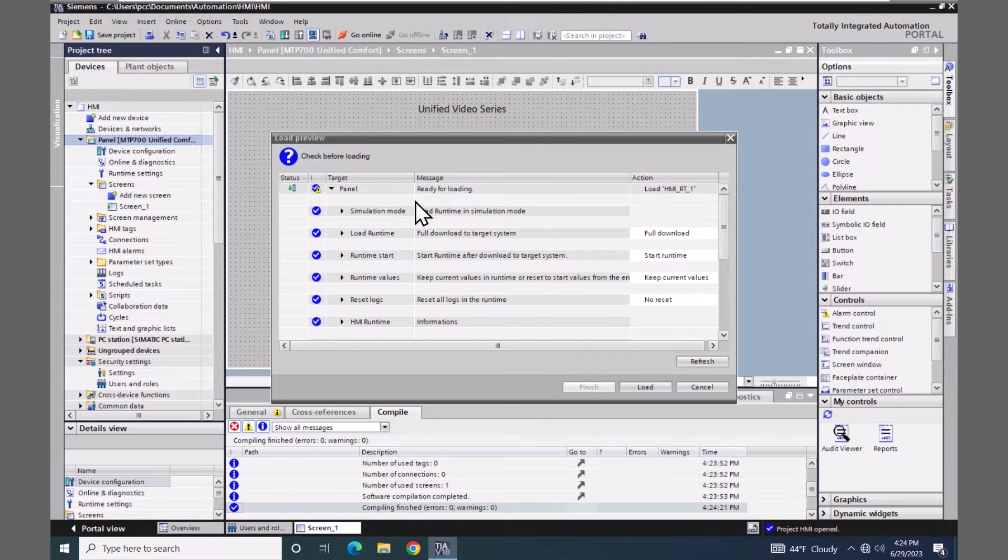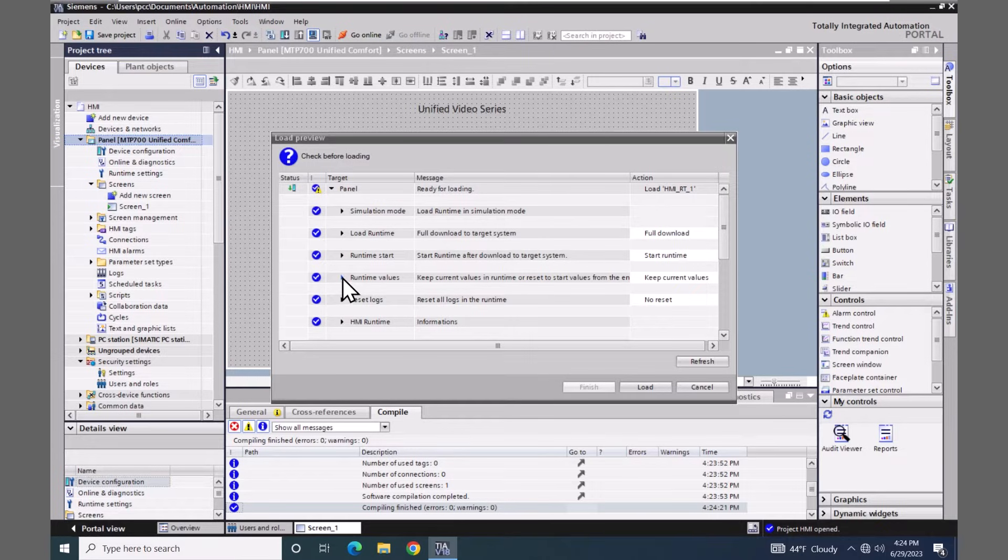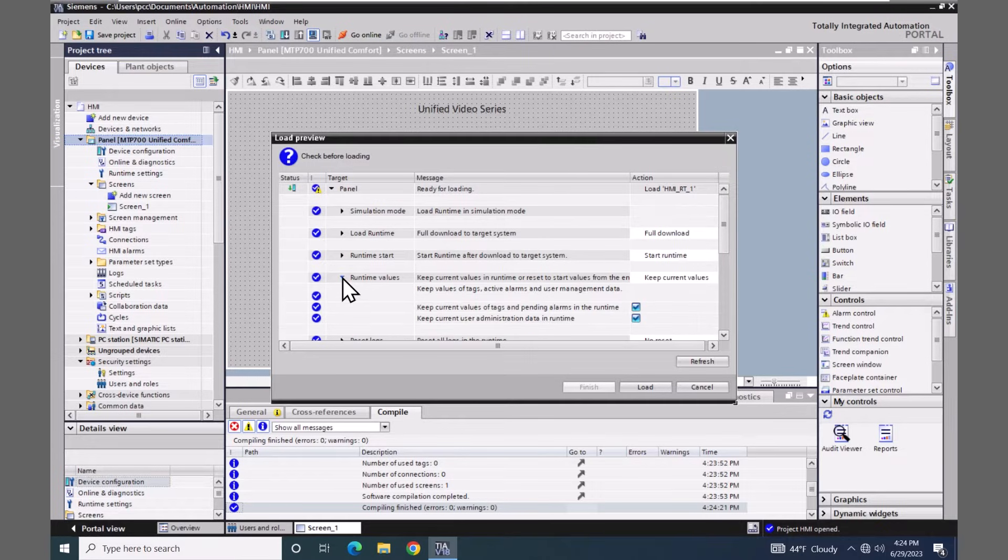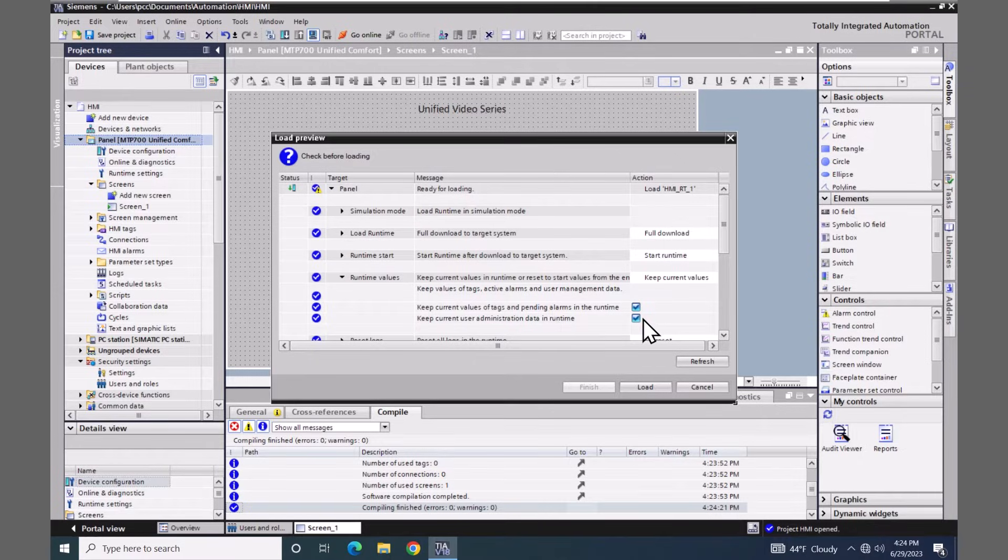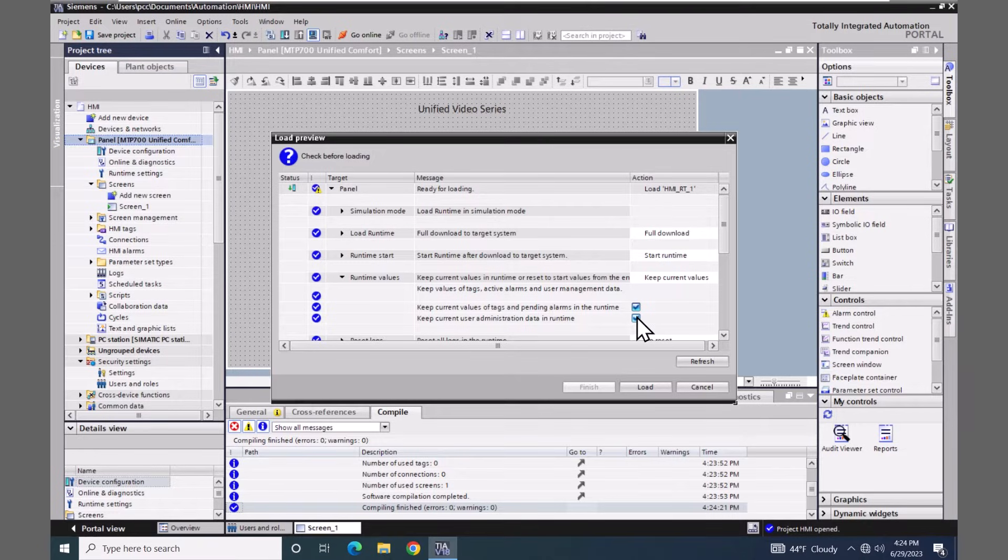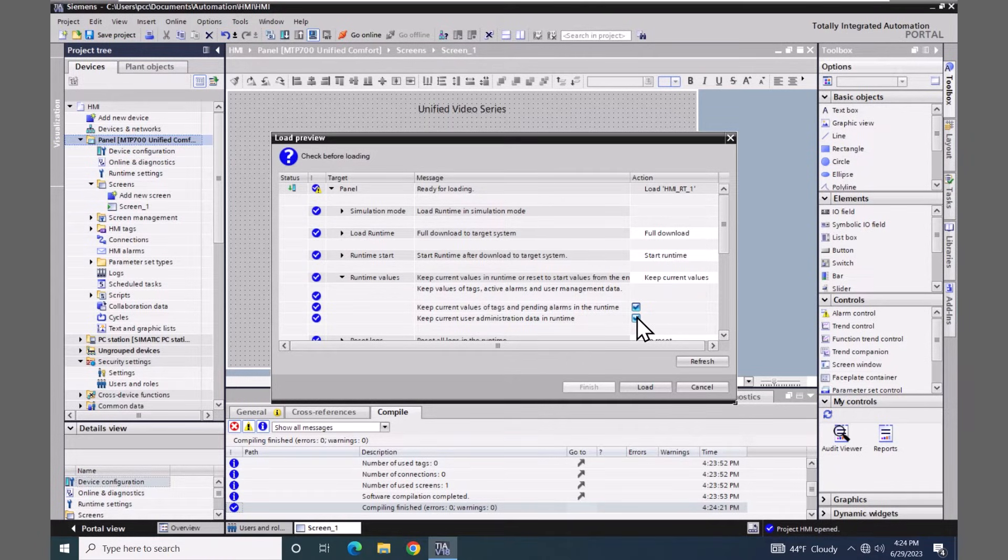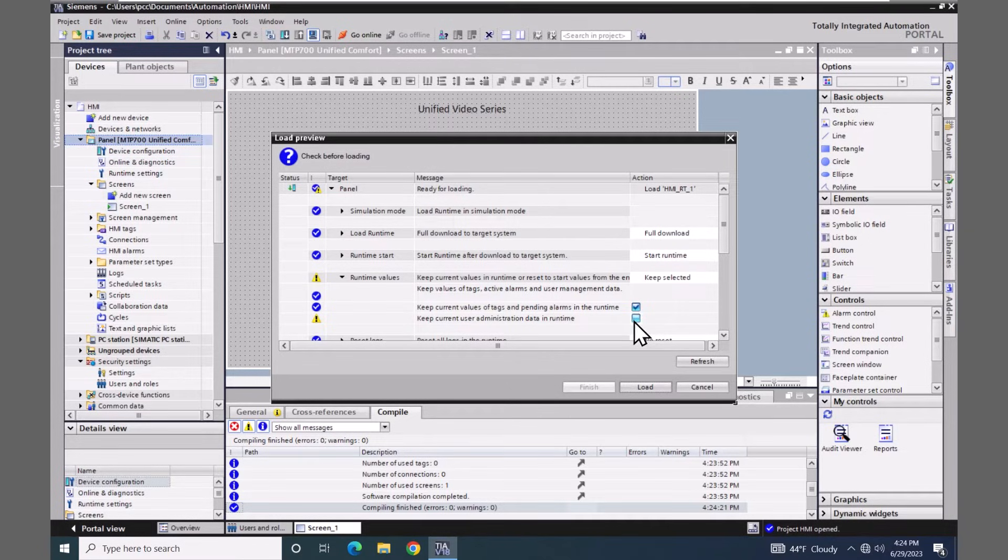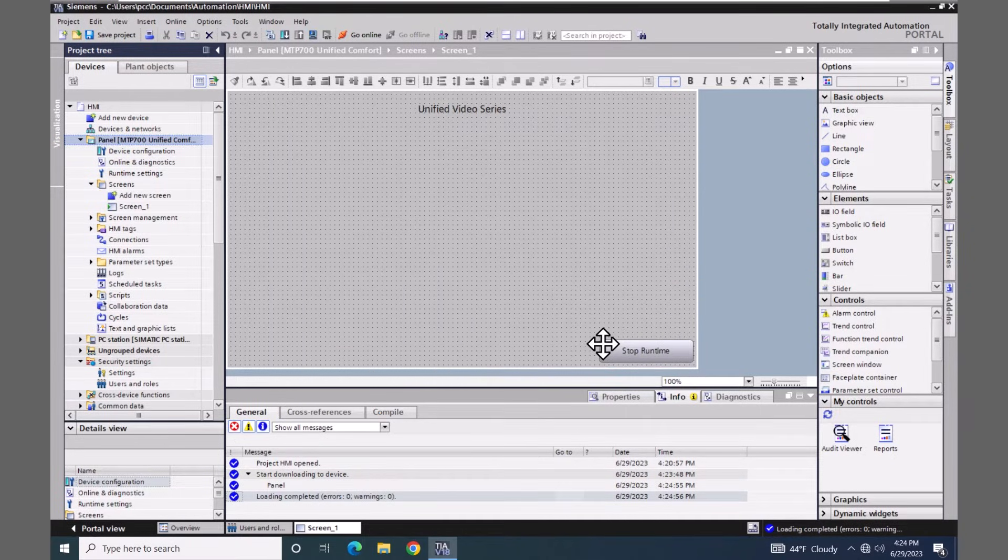When this dialog box comes up, one of the things that you're going to need to do is look for this runtime value. I will expand this out. There's a checkbox here that says keep the user administration data in runtime. If this box is checked, when I download or start the simulation, it is not going to use the new user administration from my TIA portal project. It is going to use the administration that has already previously been downloaded into the runtime environment. So I'm going to deselect this box and select load. This way, my user administration will be loaded into the simulator.